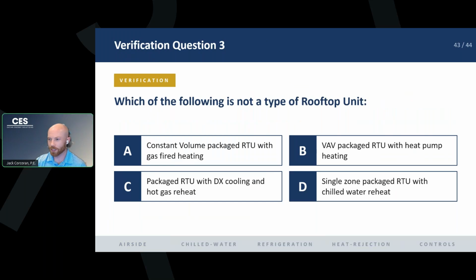And our last question, which of the following is not a type of rooftop unit, right? We mentioned that the type of heating is often a way we describe these. So constant volume packaged with gas-fired heating, VAV packaged rooftop with heat pump heating, a packaged rooftop with DX coil and hot gas reheat, or a single zone packaged rooftop with chilled water reheat. Our answer is D. There's no such thing as chilled water reheat, or at least not in a packaged rooftop. So, we know A, B, and C are types of packaged rooftops. So the answer is D.